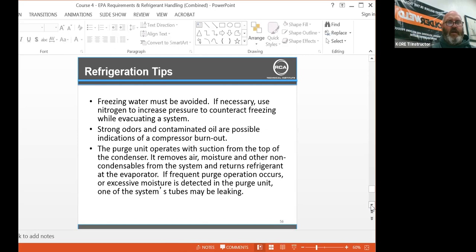Freezing water must be avoided. If necessary, use nitrogen to break the vacuum. Again, that's your blank off. Strong odors and contaminated oil are a possible indication of compressor burnout, which we know. I'm sure a bunch of guys have smelled that acid and had their entire nose catch fire because it smells so bad. Purge unit. The purge unit operates with suction from the top of the condenser. It removes air, moisture, and other non-condensables. If frequent purge operation occurs or excessive moisture is detected by the purge unit, it may be leaking.